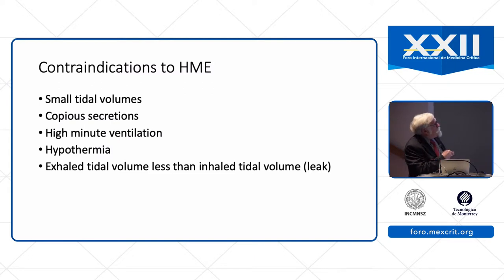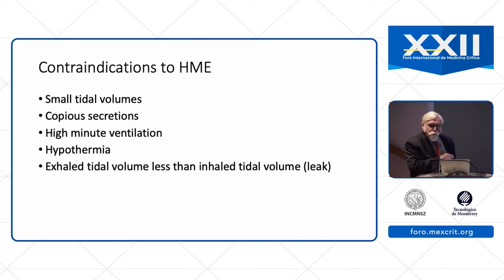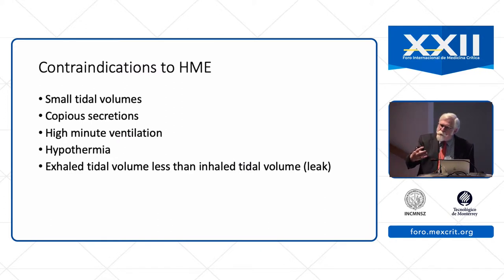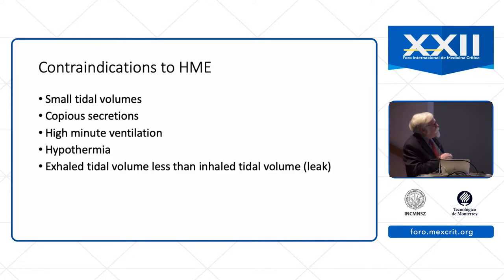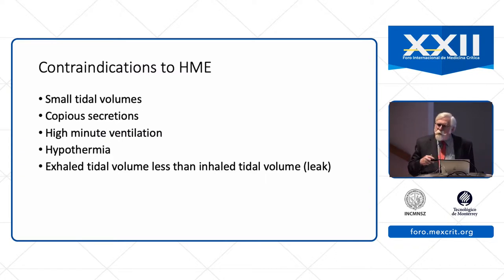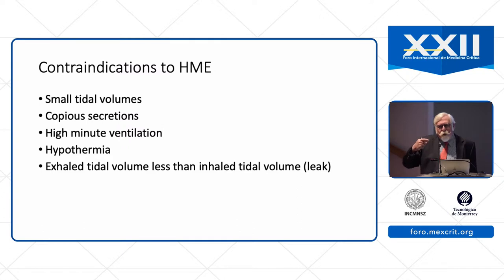With high minute ventilations, the heat and moisture exchanger is less efficient. It is less efficient with hypothermia, as it relies on trapping exhaled heat from the patient and delivering it back on the subsequent inhalation — which will not be effective if the patient is cold. These devices are also not effective if the exhaled tidal volume is less than the inhaled tidal volume, such as when there's a leak. For example, if the patient has a bronchopleural fistula with a chest tube and a large air leak, there will be less exhaled breath through the device, reducing its efficiency.